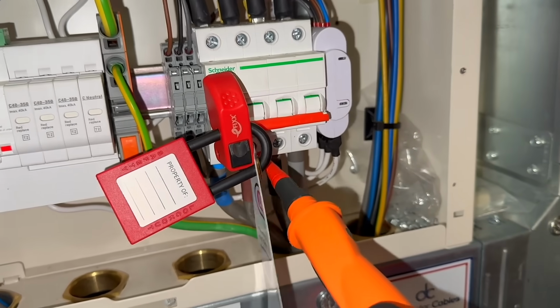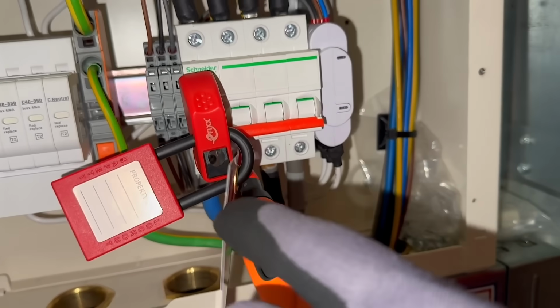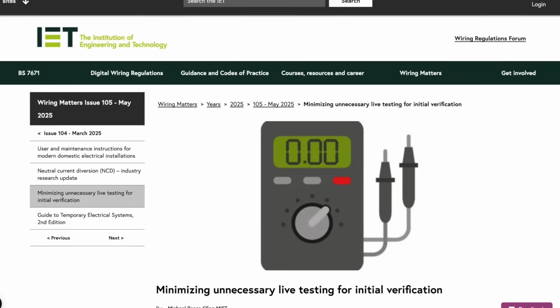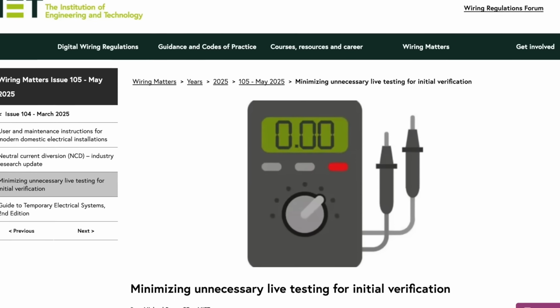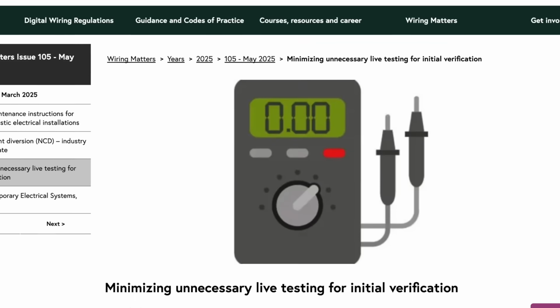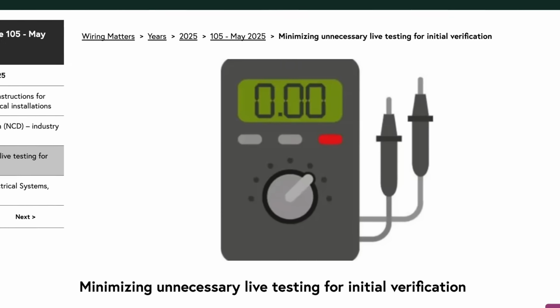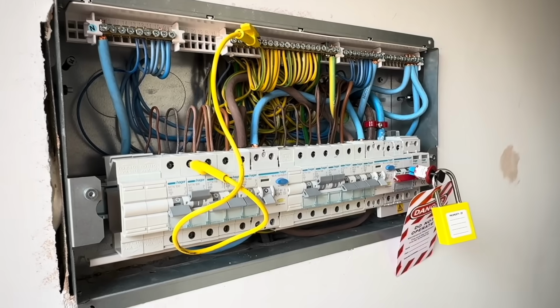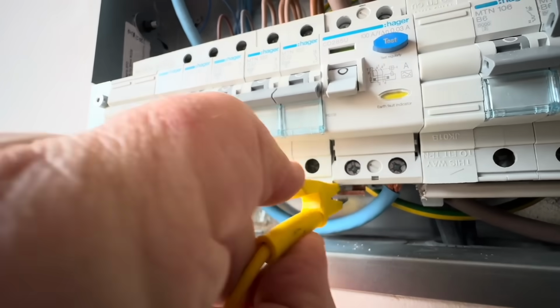The authors of the Wiring Regs have intervened in the long-running debate in the trade about live testing. In a special advisory published this week, the IET says that initial verification of circuits should not be a case of doing it the way it's always been done. The organisation says installers often carry out earth fault loop impedance testing for all circuits. This isn't necessary, says the IET, and it can be potentially dangerous.